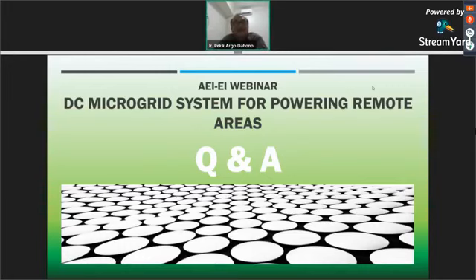In Indonesia we have a grid code for conventional microgrids. When connecting to the microgrid, as long as we can ensure our microgrid will not disturb the utility's grid, through simulation or study, the utility company will allow you to integrate your microgrid into the macrogrid. But until now in Indonesia, we have to do a detailed study if the rating of the microgrid is more than 500 kVA.